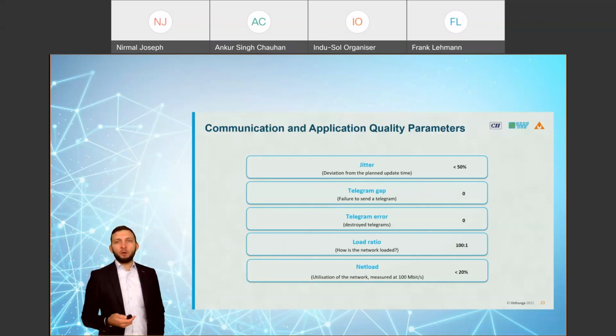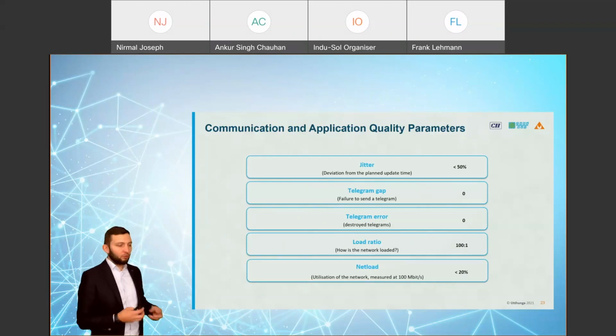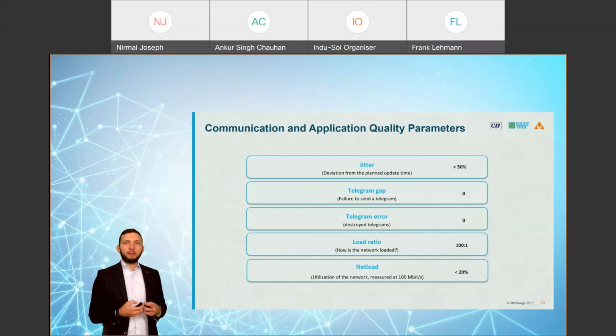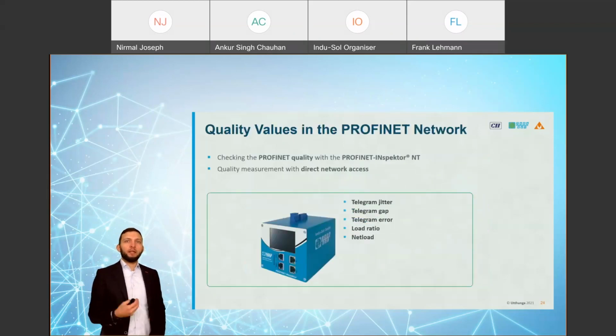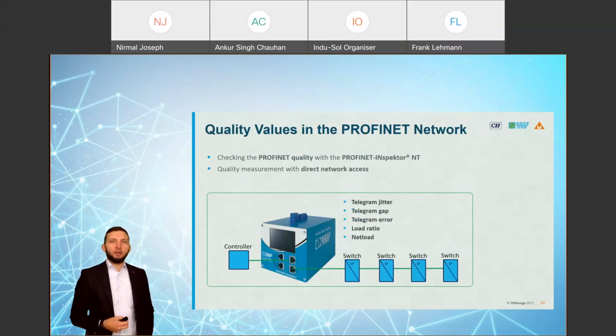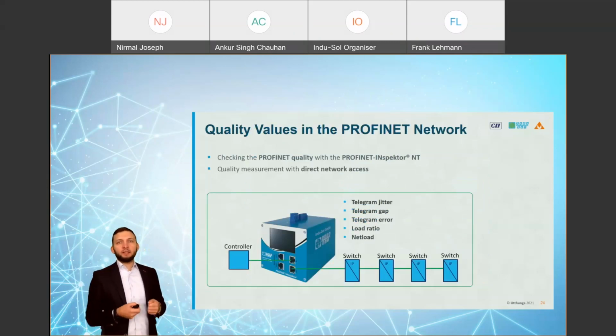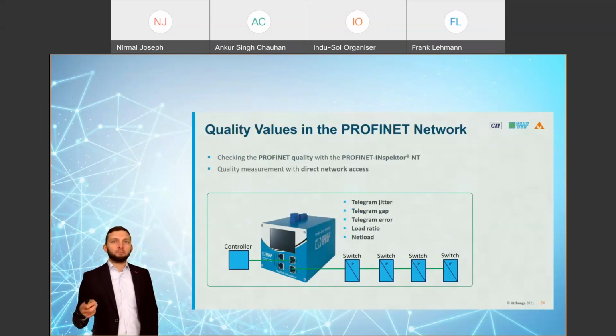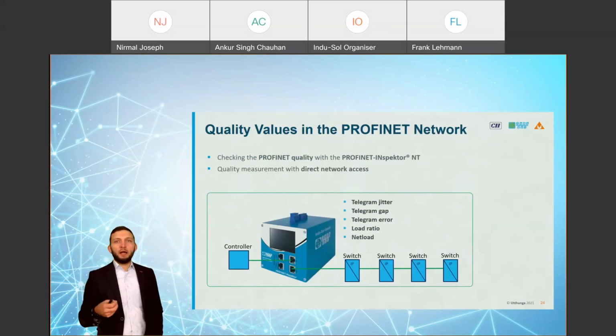The solution is very easy. I need only one tool, and I don't have to configure it. This tool automatically analyzes the whole communication between my PLC and my PROFINET network. I can connect this device to my network, and it analyzes the whole communication and describes all parameters for each device, giving me a result.